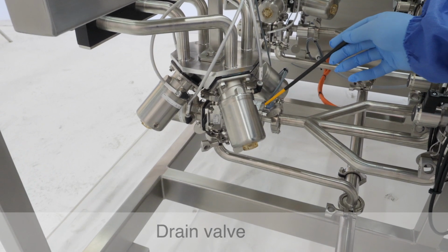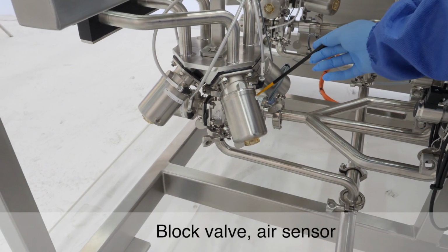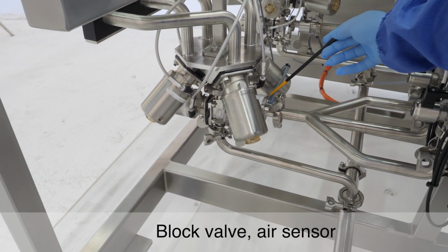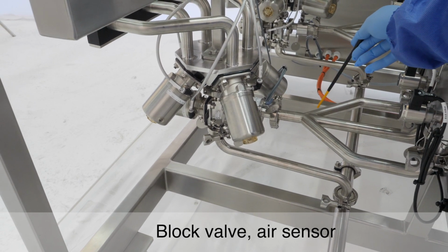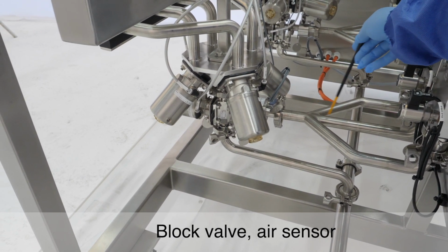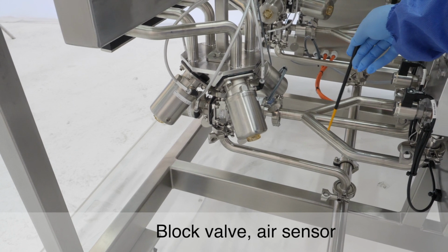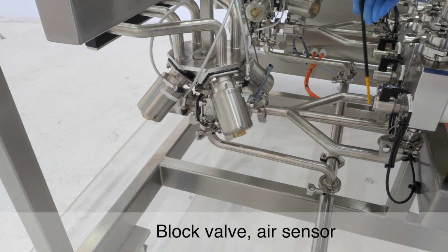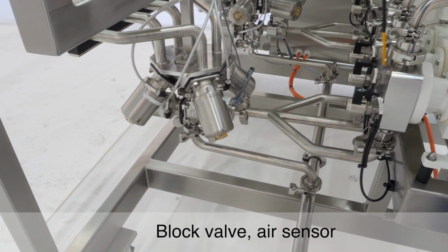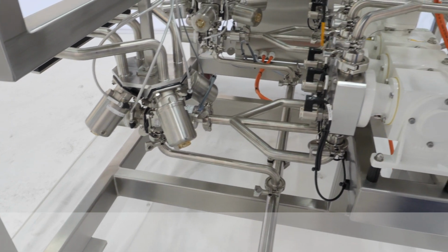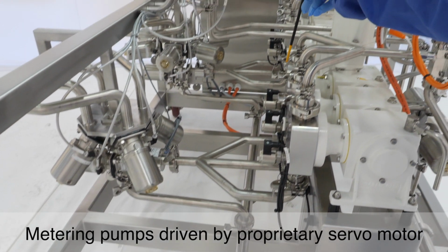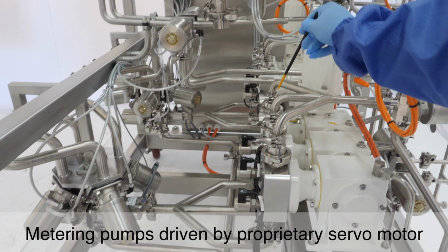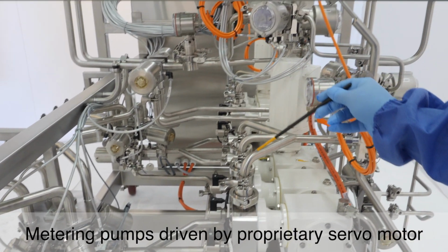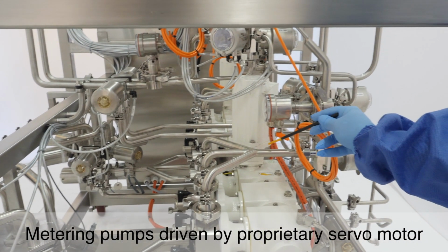From the inlet valve block, solution is passed through an air sensor to the triplex pump. Using this proprietary Y formation distribution pipe ensures even flow to and from each of the pump heads. The triplex pump diaphragm metering pumps are driven by a single servo motor, which enables the delivery of a very precise flow across large operating ranges.